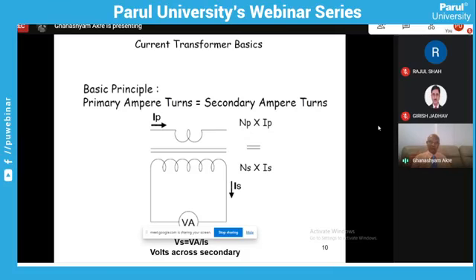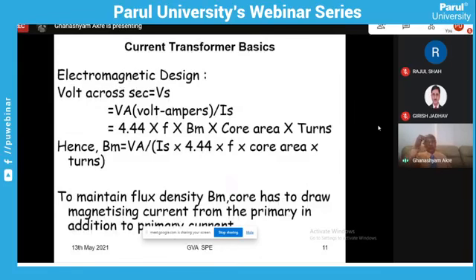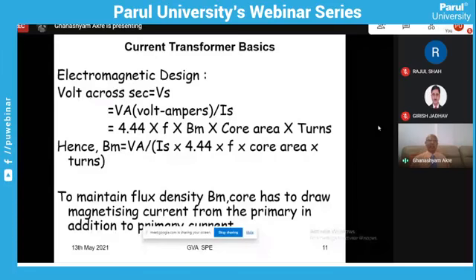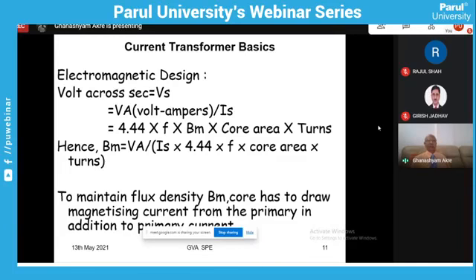Now, what is the significance of all this burden and voltage across the secondary? You see, any transformer as a function always has a primary winding, secondary winding, and the magnetic core. The primary winding is connected in this case to the primary current, so it is giving you primary ampere turns, and the secondary ampere turns depend upon the number of turns as I have explained. So in an ideal transformer, if you are passing 100 amperes, your secondary will always have exactly 1 ampere. There is no error in the ratio. But in actual fact, it does not happen. What happens is that when you are giving the primary current, the core, the magnetic circuit itself, will draw its own excitation current, which is required for magnetizing, and for overcoming the eddy currents and the watt losses in the magnetic core.